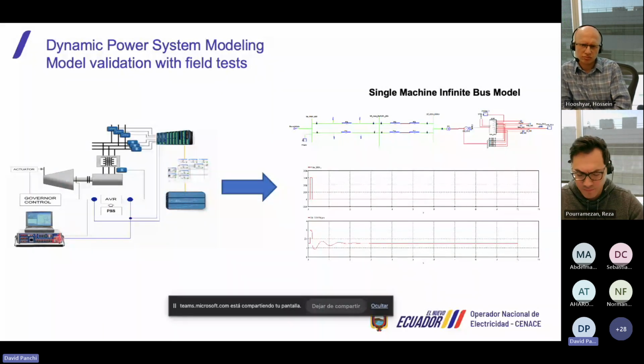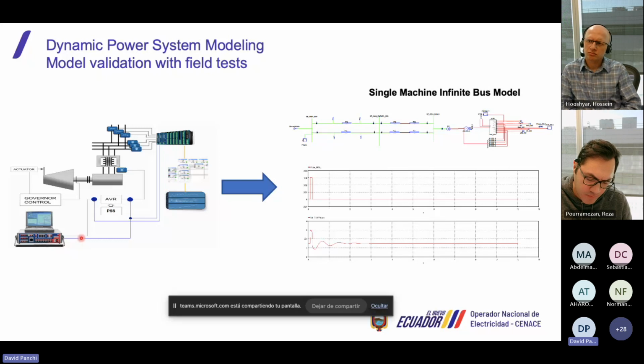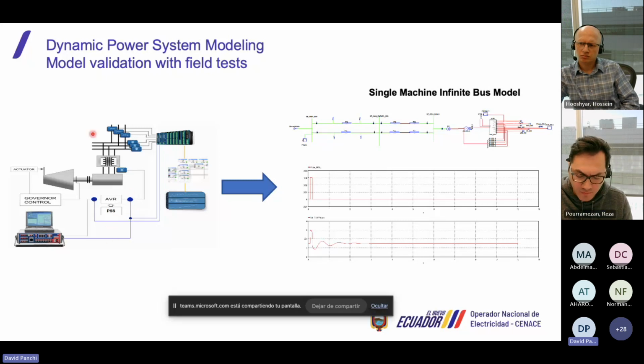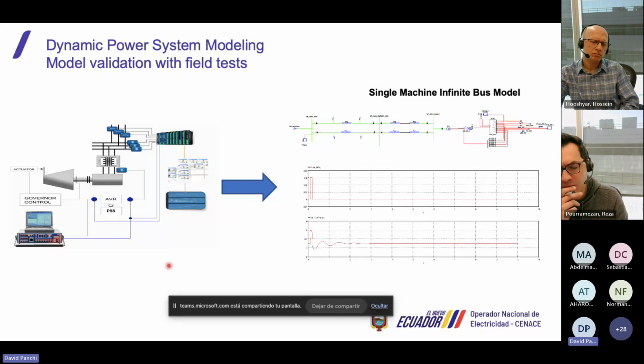So we do the frequency step in the simulation, but the voltage is constant. We use 60 hertz here in Ecuador, and we do a step of about 1%, 2.5% to the governor. And the AVR is the same, but we move the voltage. We do a step in the voltage, the same as 110 volts here, but with the power plant in line with load.